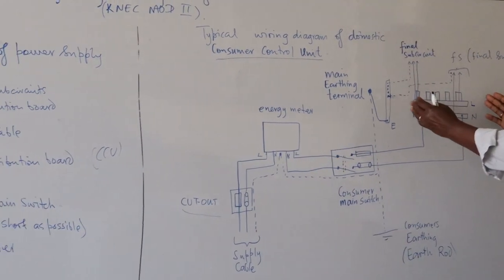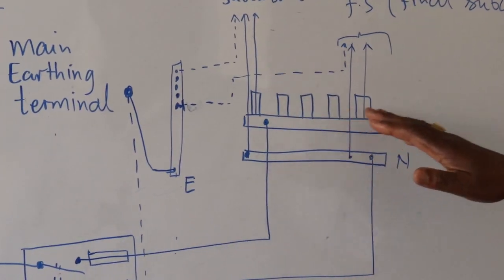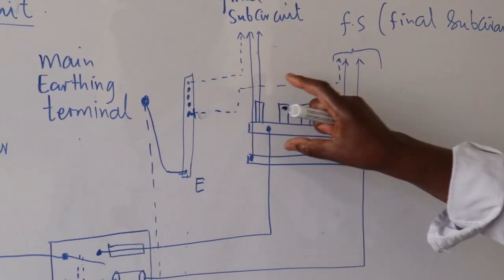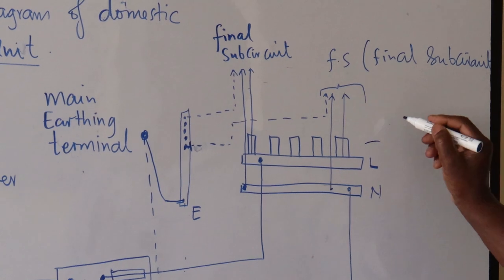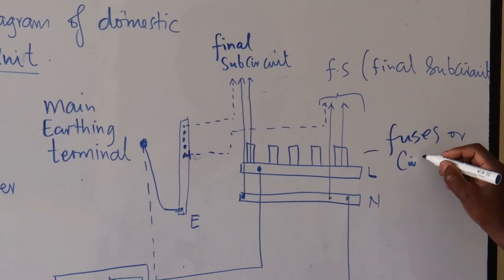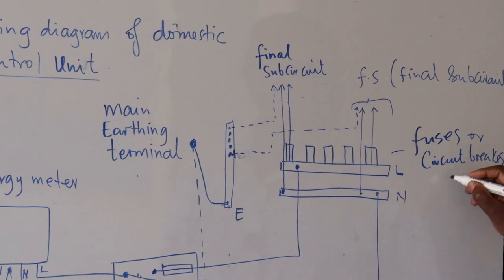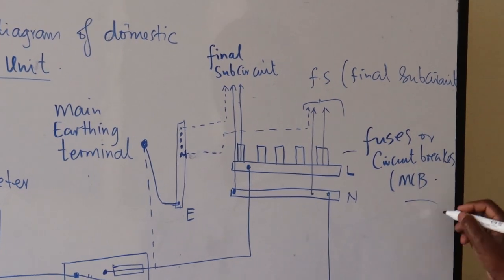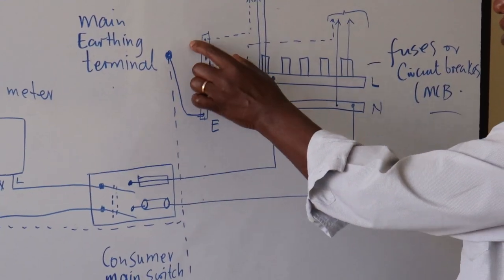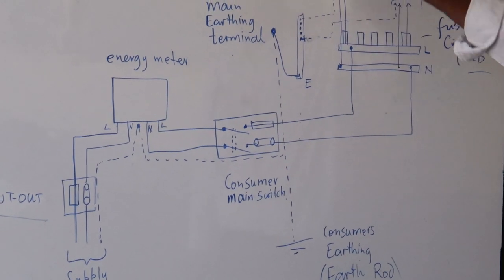If it's a small installation, this will be either six or four final sub-circuits. We have a live busbar connected. Now we can have fuses — the common trend nowadays is to have circuit breakers, sometimes referred to as MCBs. And then we have a neutral busbar where we take off our neutrals, and an earth busbar where we take off our ECC, the earthing continuity conductor.